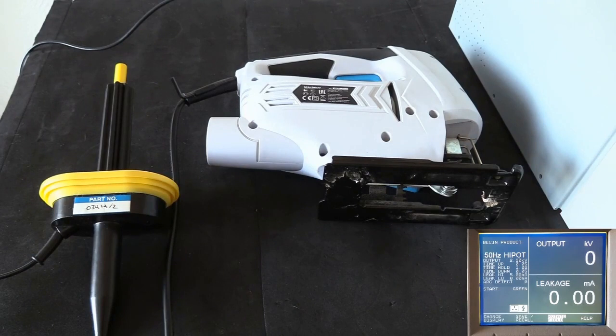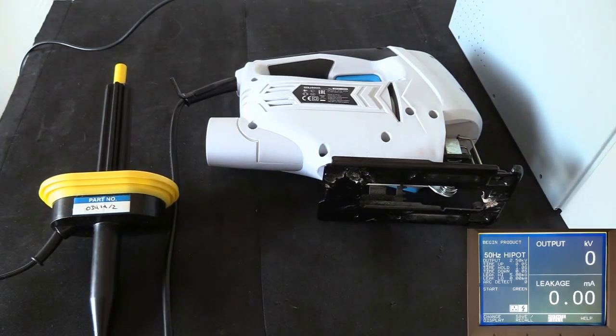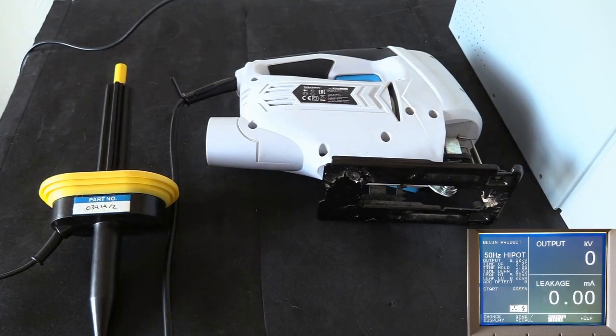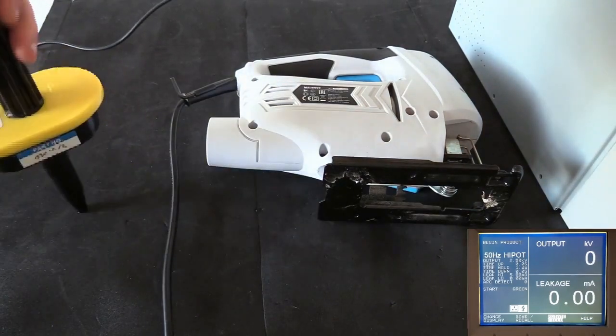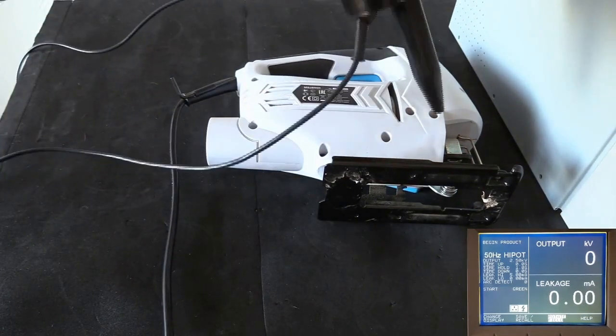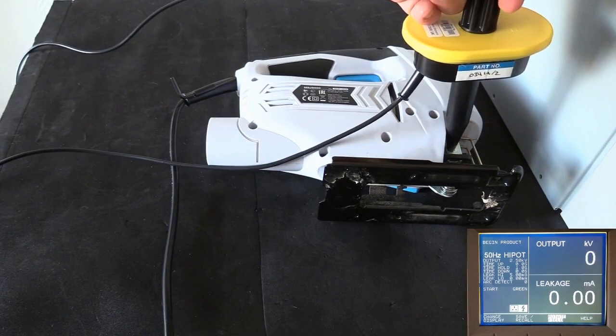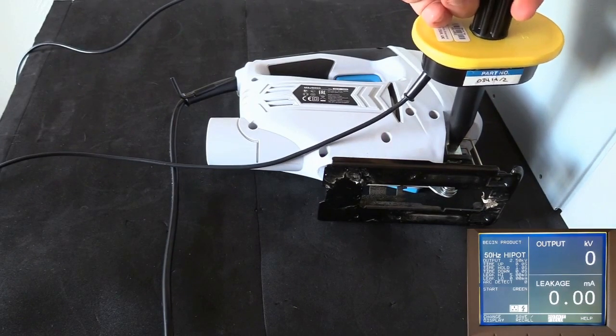In terms of the test parameters themselves, because this is double insulated, we tend to test at a higher voltage, usually twice that of the class 1 variant. So in this particular example today, we're going to be testing this at 2,500 volts. We're going to be testing each point for 1 second, and providing the leakage is less than 5 milliamps, then everything will be good. So let's go ahead and start with our first exposed metal point. We'll take our probe, place it onto the metal point, and then we can start the test.